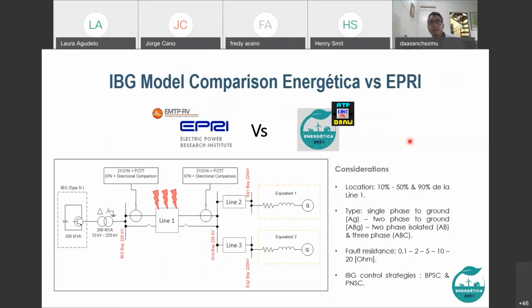So, in this exercise, we use a study case. The study case is presented here, and the fault events were defined using these considerations: locations at 10, 20, 50 and 90% of the line, 4 types of faults: single phase to ground, 2 phase to ground, 2 phase isolated, and 3 phase, different fault resistances from 0.1 to 20 ohms, and 2 IBG control strategies, BPSC and PNSC.